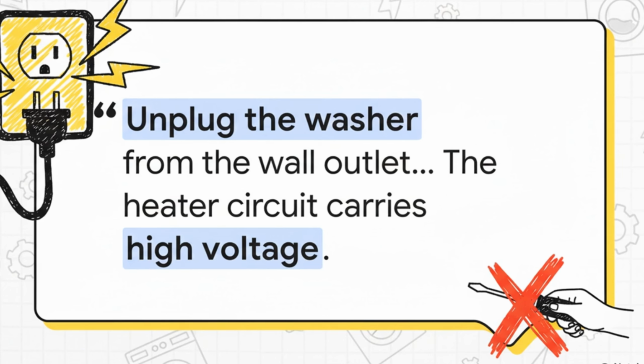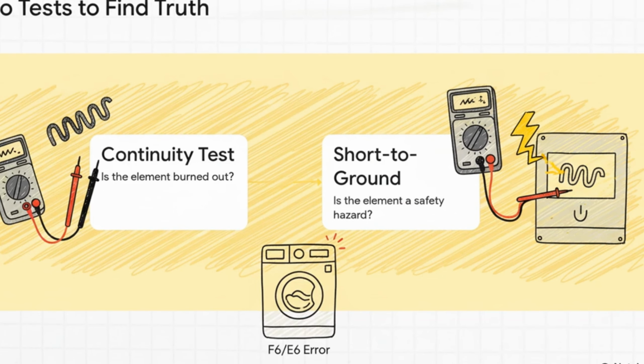Seriously, no shortcuts. With the machine totally unplugged, we're going to run two really simple tests using a multimeter. The first test tells us if the element is just burned out. The second one, which is a critical safety check, tells us if it's shorting out and has become dangerous. Together, these two tests will give us our definitive answer.